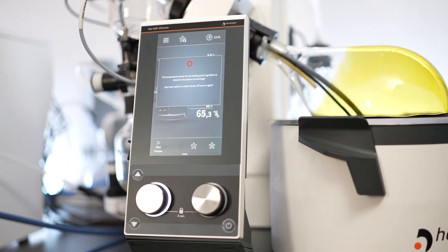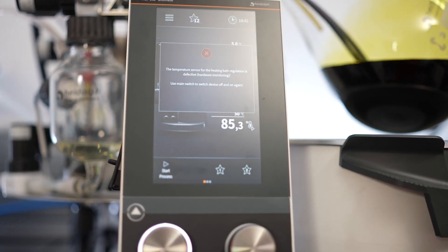Thank you Jakob. All process data can be recorded and saved, and all materials in active and passive contact with the media are FDA conformant. The entire system is made and certified for continuous unattended operation, and by using overpressure instead of a pump we avoid a potential contamination risk from pump heads. Several safety features are included so that the entire system will stop the process as soon as any malfunction or critical process situation is detected, whether from the Distimatic Pro or from the rotary evaporator.